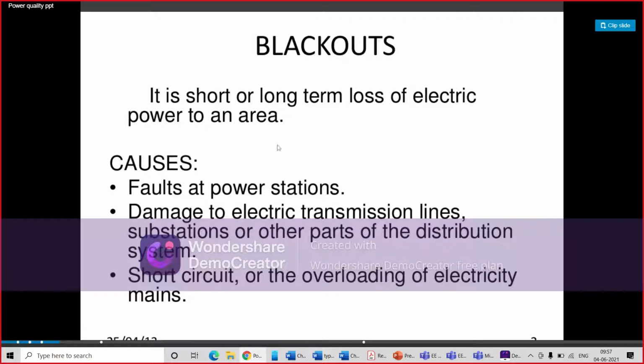And what are the different causes? What can cause blackout? Fault at power station, damage to electrical transmission line, substation or other part of the distribution system, short circuit or the overloading of electrical mains. So any one of them could be the cause of your blackout. So what are the effects of blackout? What will your blackout lead to? It will lead to the total loss of power to an area, a tripping of substations, and under certain condition network component shutting down can cause current fluctuation in neighboring segments of the network, leading to cascading failures of larger section of the network. This may range from a building to a block to an entire city to an entire electrical grid. So it has a wide area of effect.